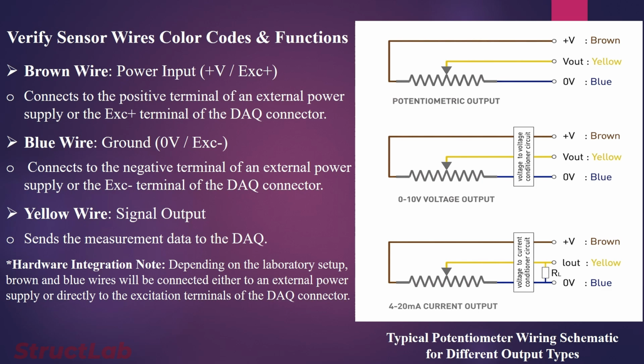Step 2. Map out the sensor's wire color codes and their functions. Looking at the schematic on the right, the pinout layout remains consistent across output variations. Brown wire. This is the positive power input, or excitation plus. Depending on your setup, it connects either to the positive terminal of an external power supply or directly to the DAQ's EXC plus pin. Blue wire. This serves as the 0 volt ground return, or excitation minus, connecting to either the negative power supply terminal or the DAQ's EXC minus pin.